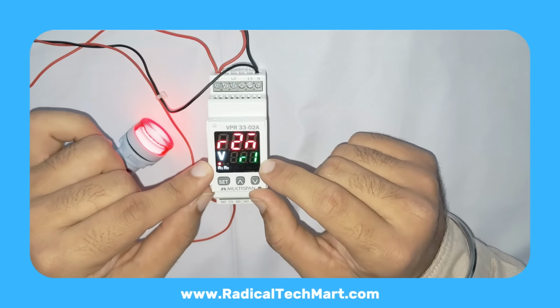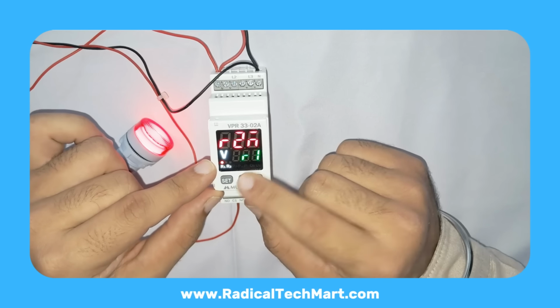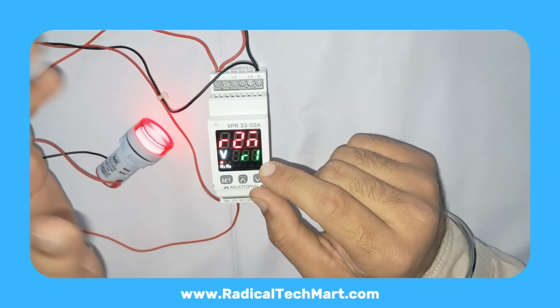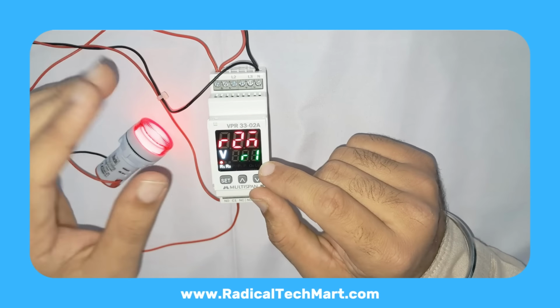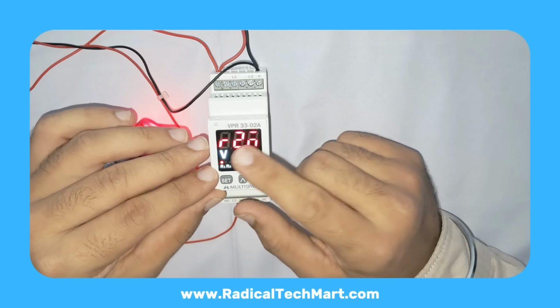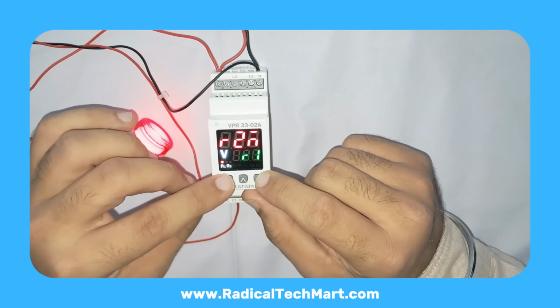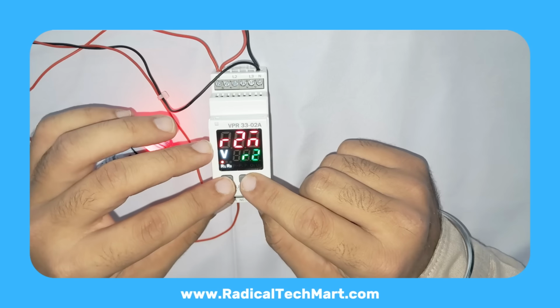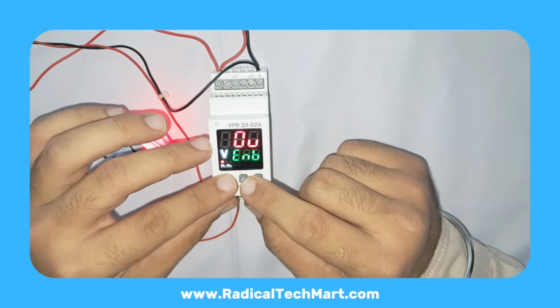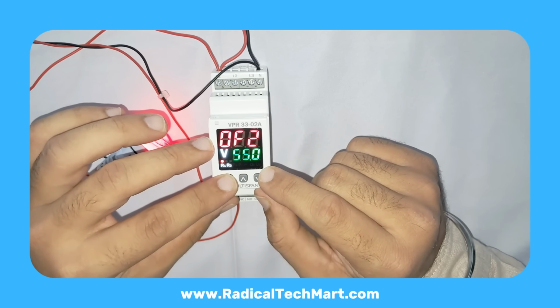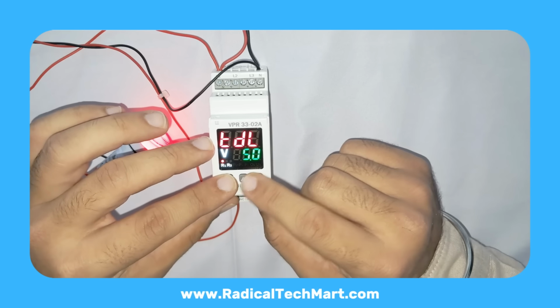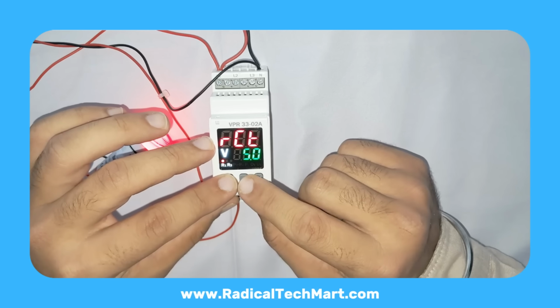If you want R1 and R2 to follow the same settings, we have a shortcut. There is an option where you can select R1 for copying. So all the parameters you set in relay 1 will be copied to relay 2. If you select R2 there instead, then you must set all relay 2 parameters individually. For this demo, we keep relay 2 the same as relay 1.